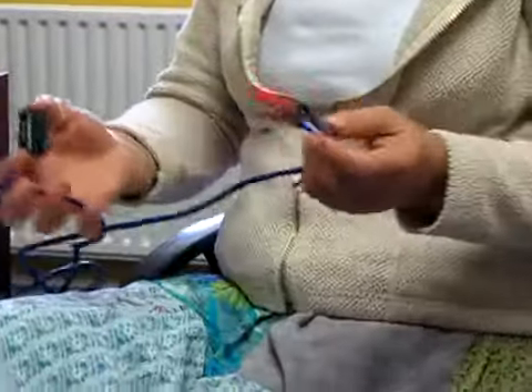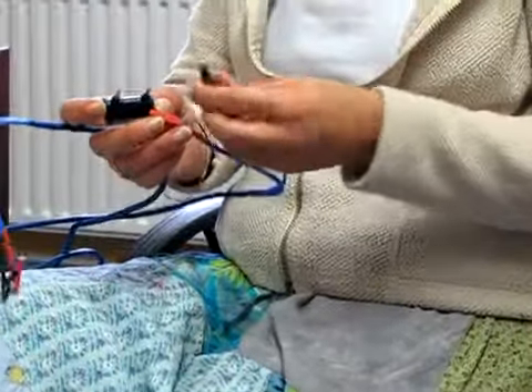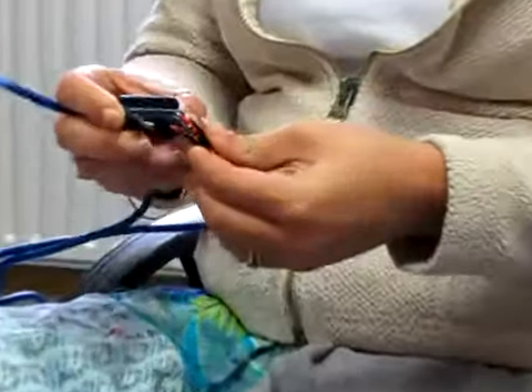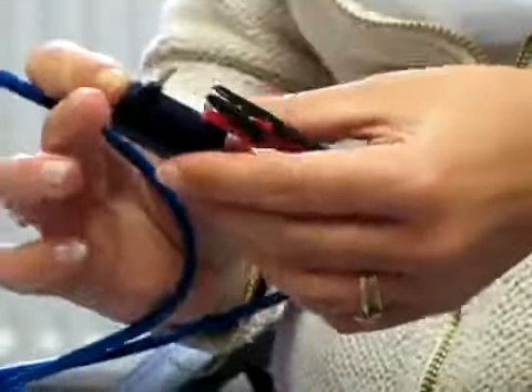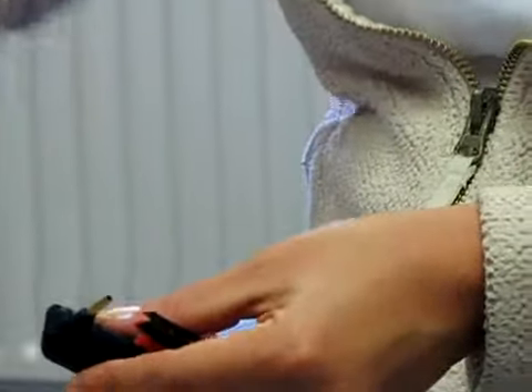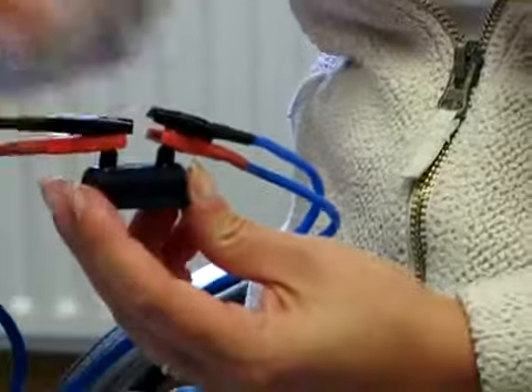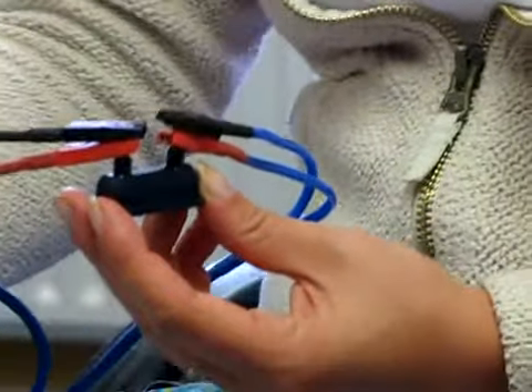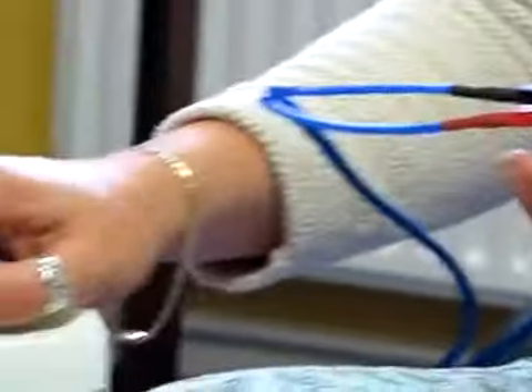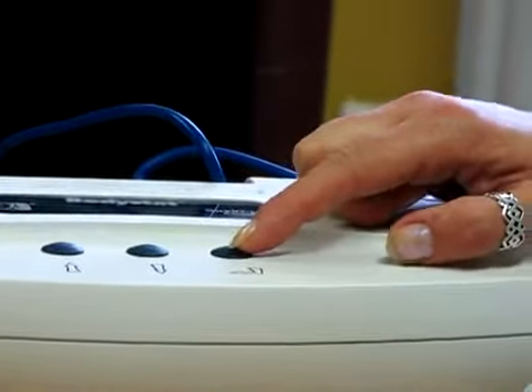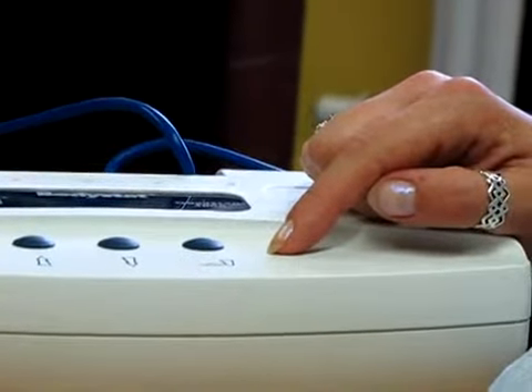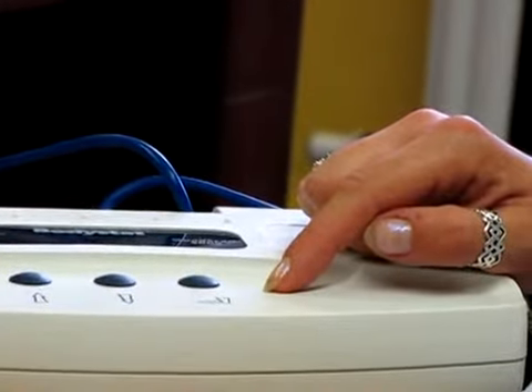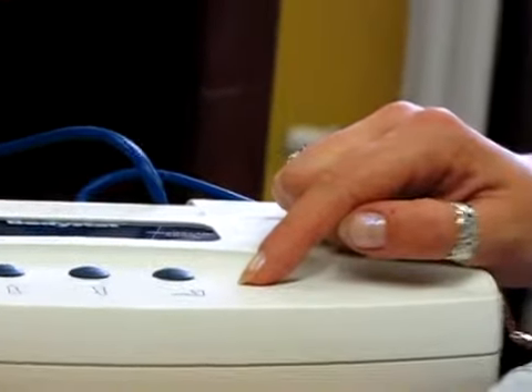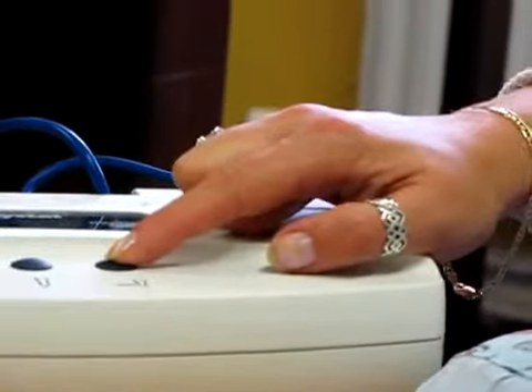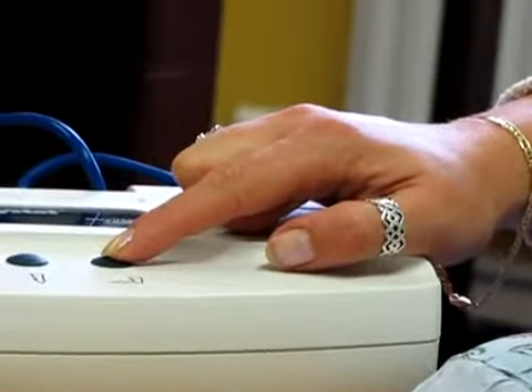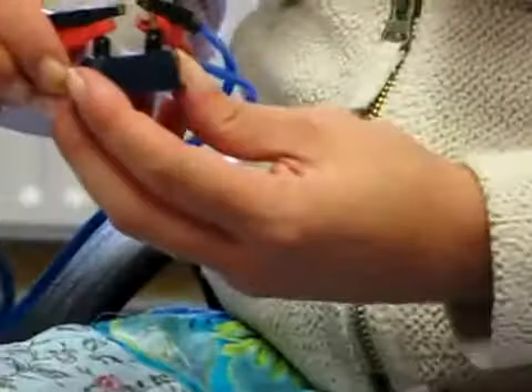All you do is take one of your lead wires and attach the crocodile clips to either side. Once you've done that, switch the device on, click through all the parameters and do a normal test. Once the test is complete, click through until you see the ohms, and it should read between 497 and 503.